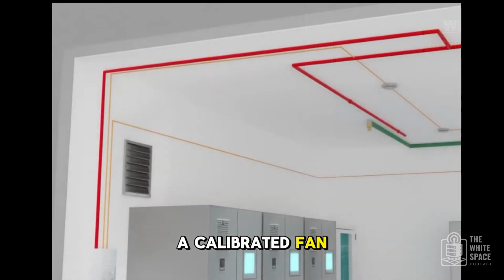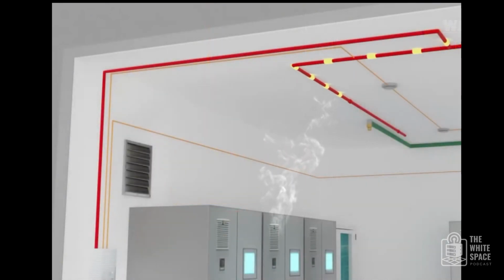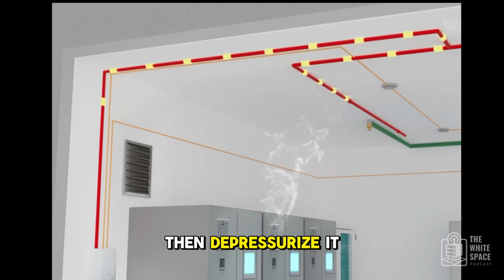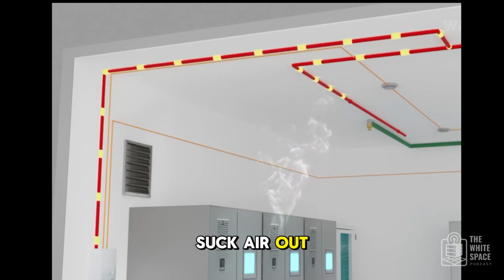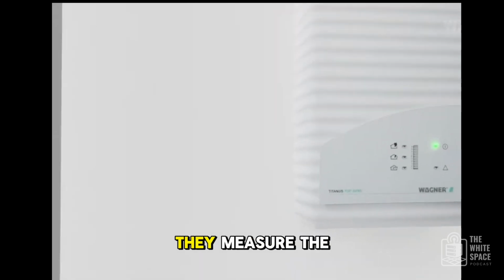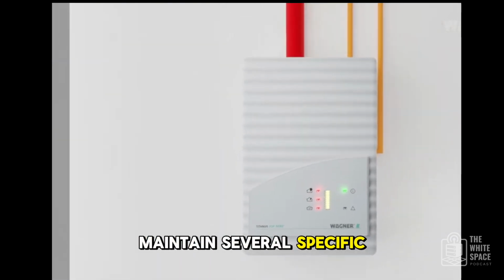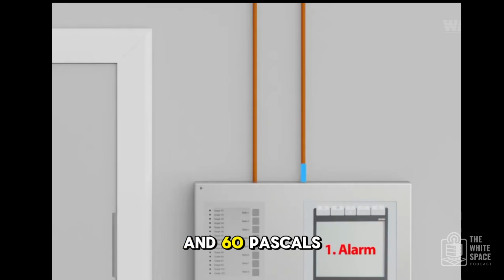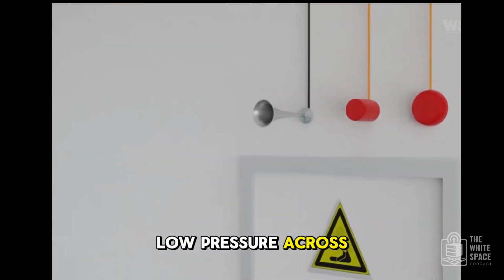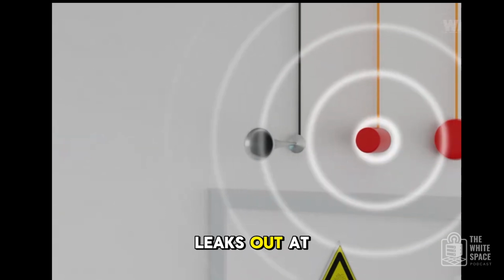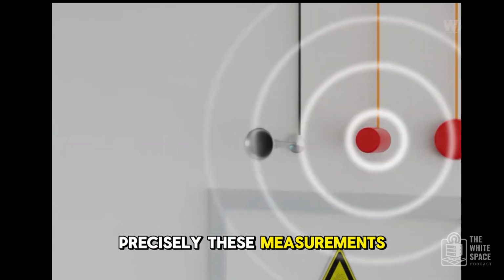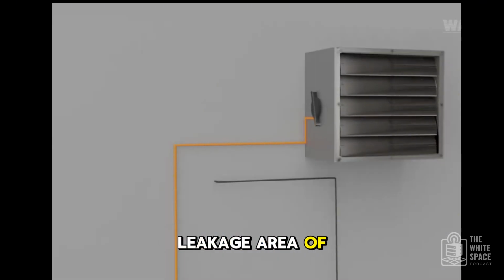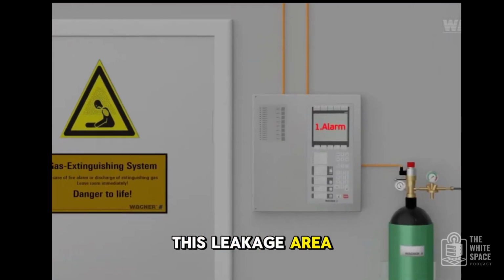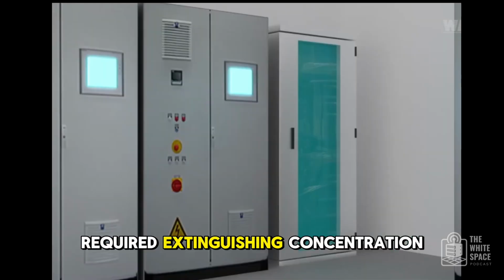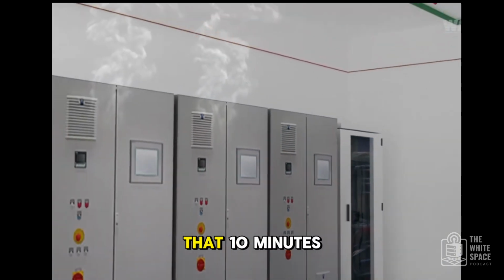Then they use a calibrated fan unit, usually fitted into a doorway, to pressurize the room slightly and then depressurize it. Okay. Blow air in, suck air out? Basically, yes. While doing this, they measure the airflow needed to maintain several specific small pressure differences, usually between 10 and 60 pascals, which is very low pressure across the room's enclosure. So they're measuring how much air leaks out at different pressures. Precisely. These measurements allow them to calculate the total leakage area of the room. Software then uses this leakage area, the room volume, and the specific gas agent's properties to predict how long the required extinguishing concentration will be held. And it needs to hold for that 10 minutes.